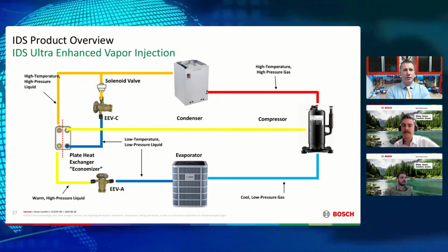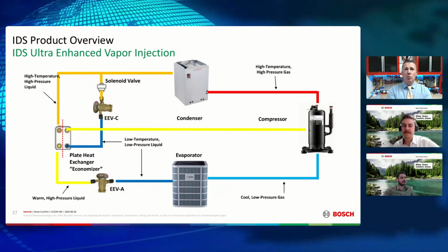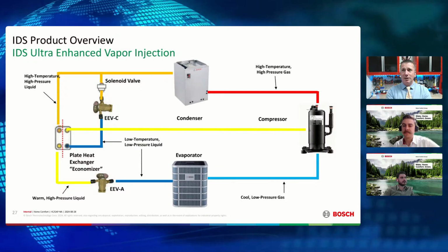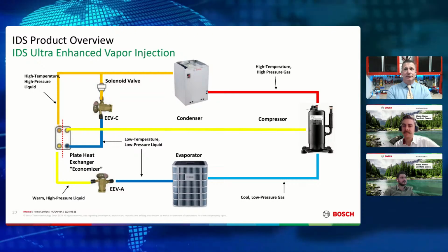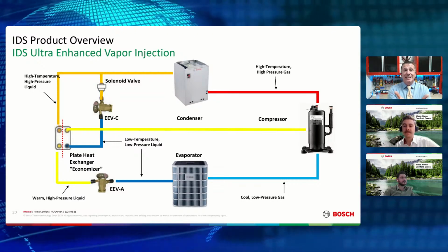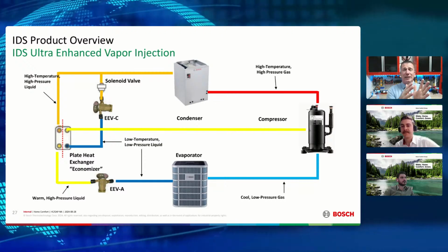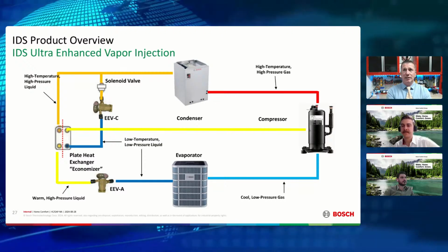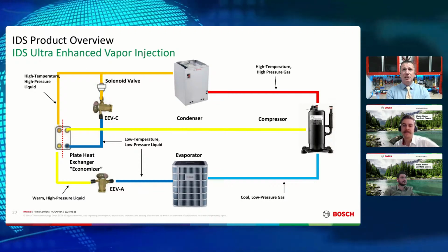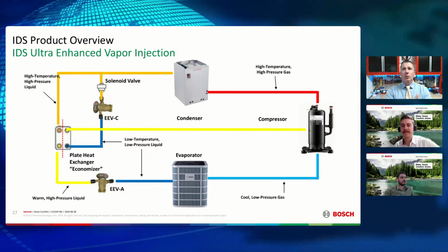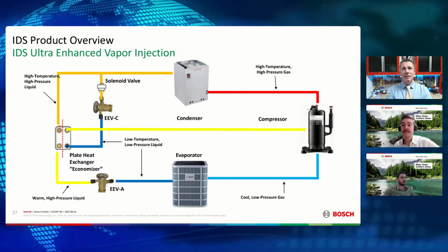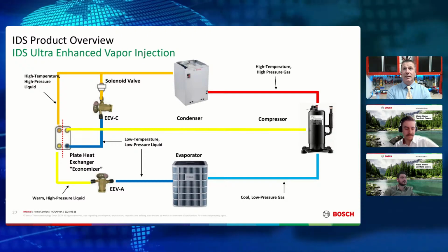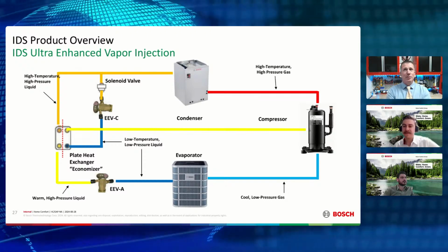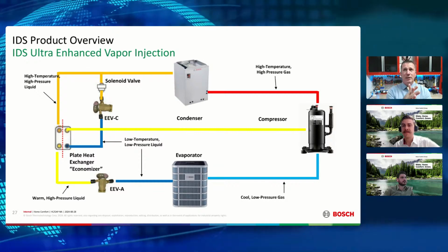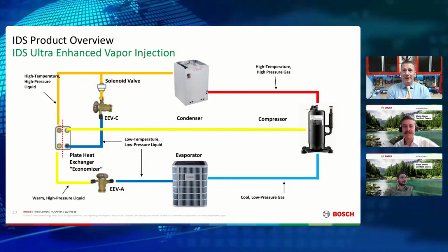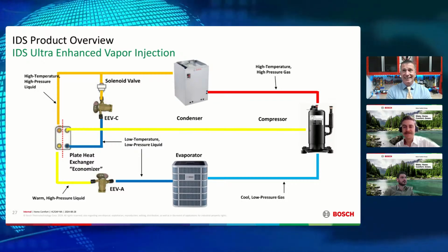If we talk about a traditional single stage or two stage unit, and we wanted to adjust our evaporator target temperature, we simply changed fan speed, right? Because our capacity didn't change. So we changed our sensible heat ratio by changing the airflow across the evaporator. Many technicians are stuck with that same mentality when they get into inverter technology and say, "Oh, I'm not dehumidifying enough. I'll just reduce my fan speed like I used to," not realizing that because we have target evaporator temperatures, if I reduce fan speed, all I'm doing is reducing capacity. Yep, that's it.